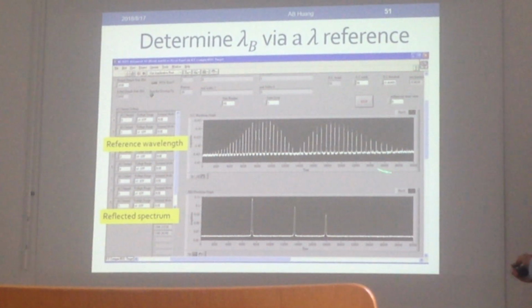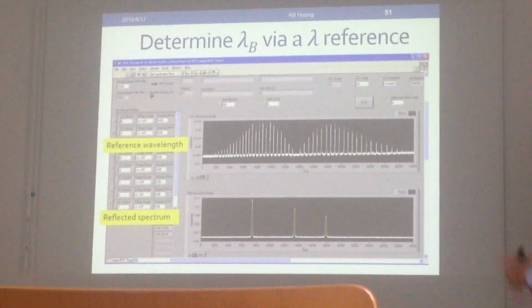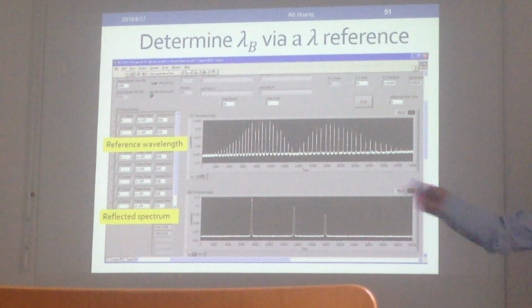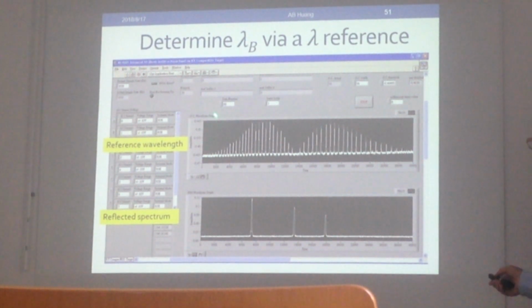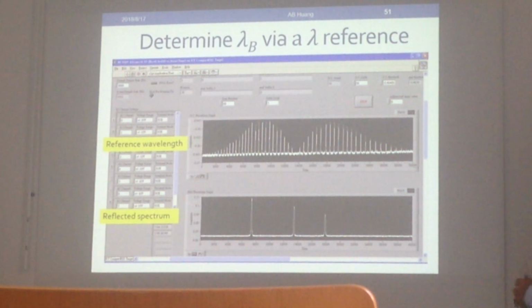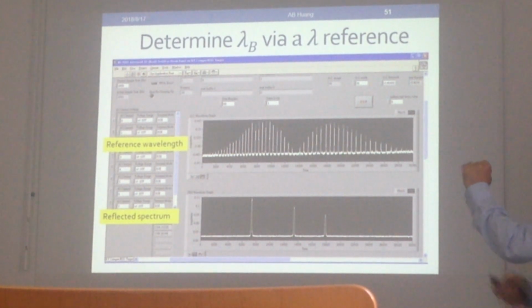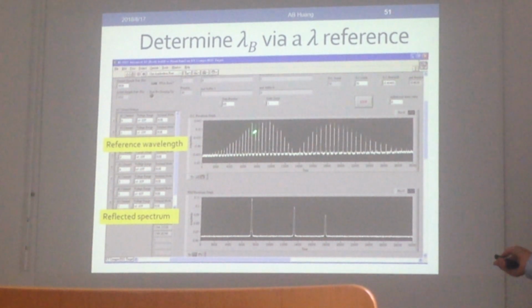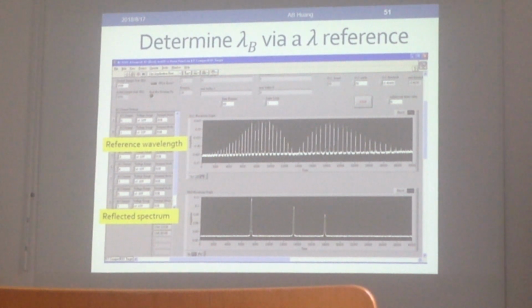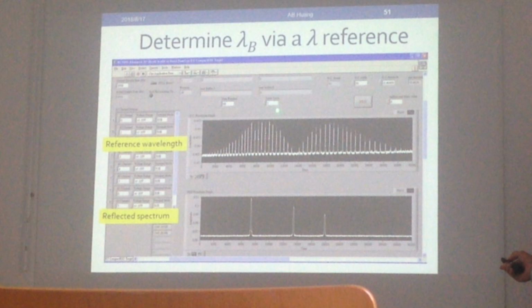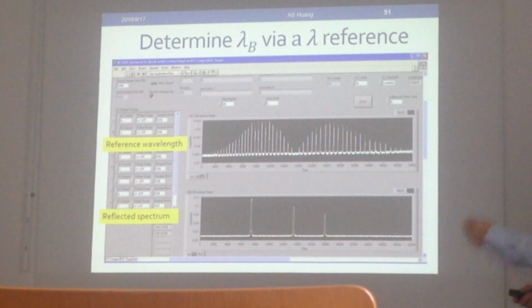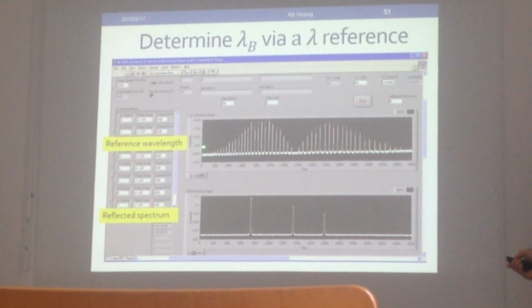This is good and bad. We use what we call a wavelength reference. Whenever we take readings, we split the light, one into the optical fiber that has the FBG sensors, the other one to this wavelength reference. In this case, it was a little gas chamber. In that gas chamber, it absorbs light at certain wavelengths. What's left is reflected back or passed through the chamber. The important thing is the peak that passed through the chamber has a very unique wavelength. It's the gas, it's the chemical optical reaction. So every peak wavelength is known. The manufacturer provides you a list, a sort of data sheet you can feed into your computer.